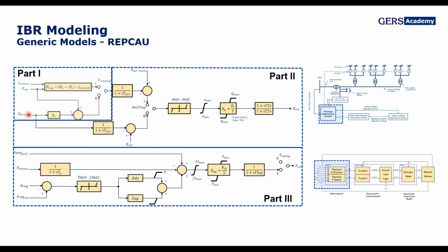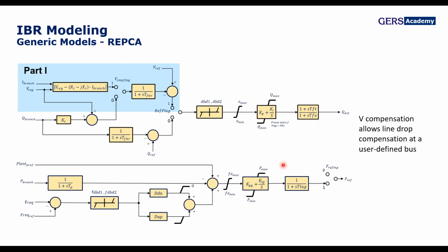The other one allows a PI controller that actually generates reactive power references, and the other that is independent is the active power. As you see here, you have the capability of allowing an active power drop depending on the frequency, or just having a fixed response for the active power branch. What is interesting in the inverter models is that you decouple the signals between active and reactive power.